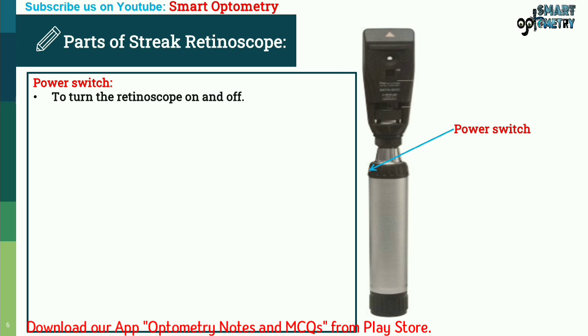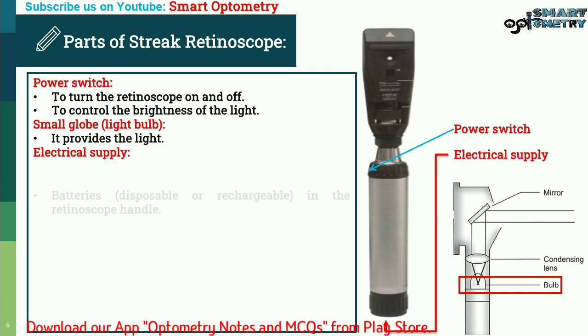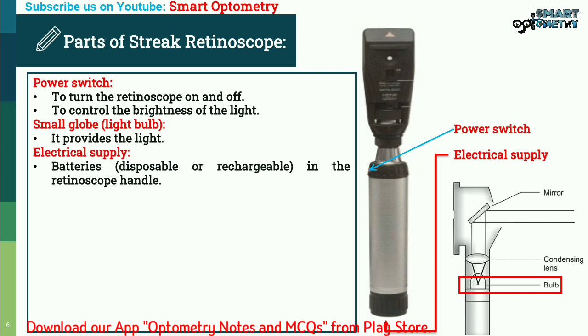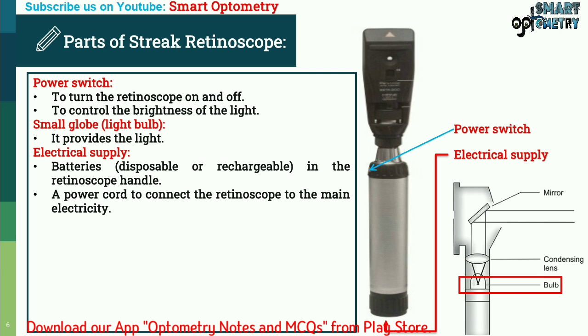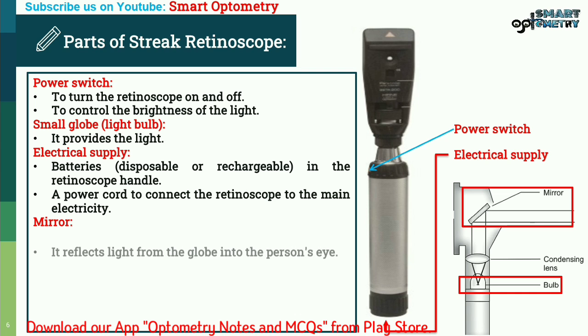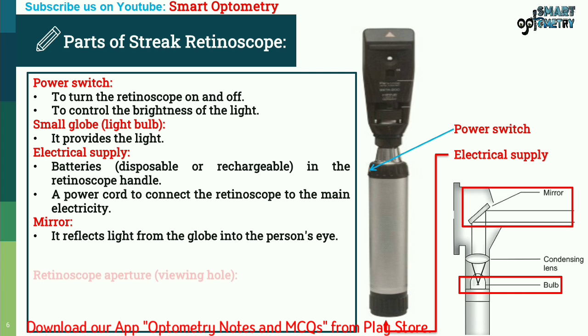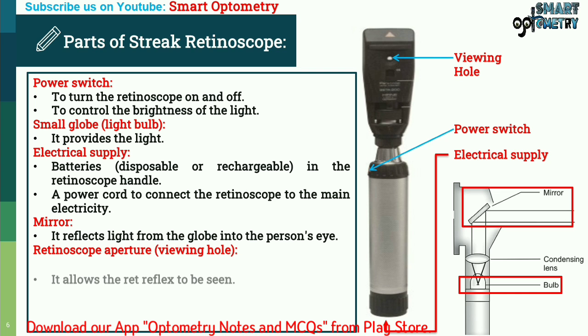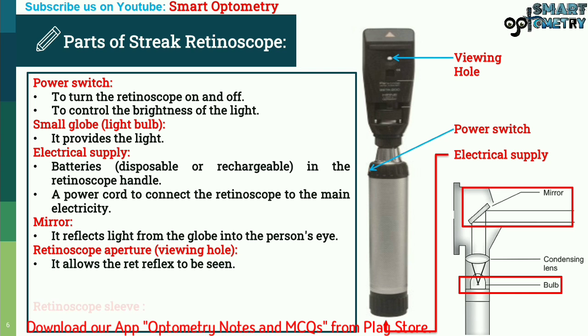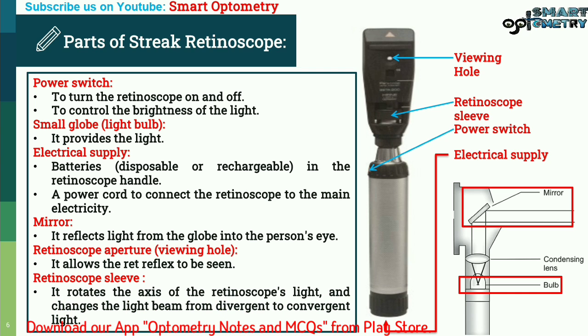The parts of the streak retinoscope are: the power switch, to turn the retinoscope on and off and control brightness of the light; the small globe or light bulb, which provides the light; the electrical supply, consisting of batteries — disposable or rechargeable — in the retinoscope handle, or a power cord to connect to the main electricity; the mirror, which reflects the light from the globe into the person's eye; the retinoscope aperture or viewing hole, which allows the red reflex to be seen; and the retinoscope sleeve, which rotates the axis of the retinoscope light and changes the light beam from divergence to convergence.